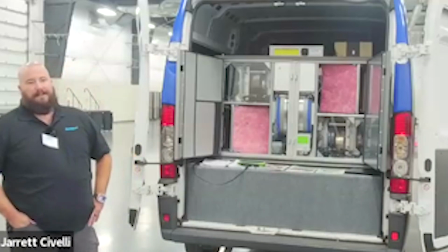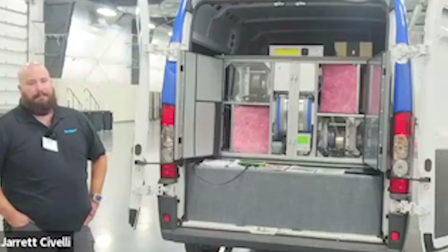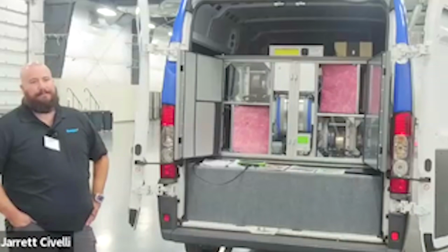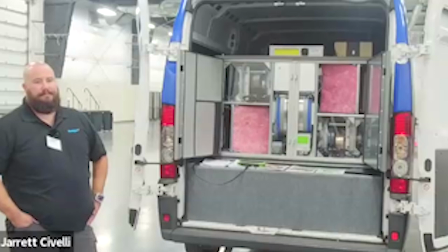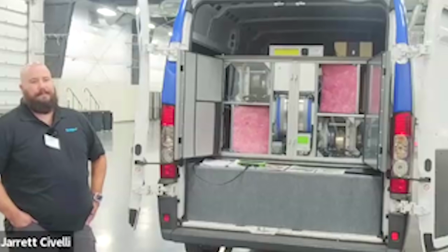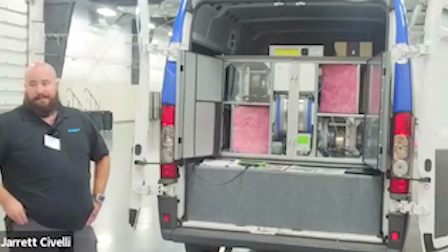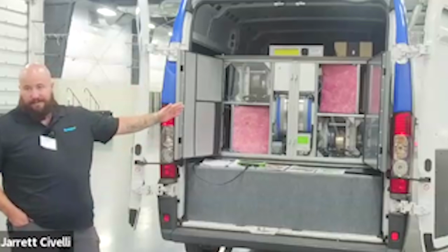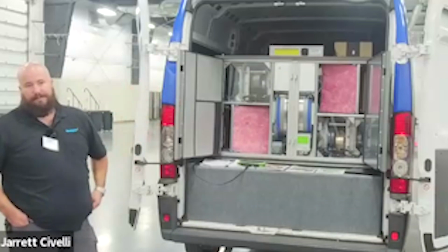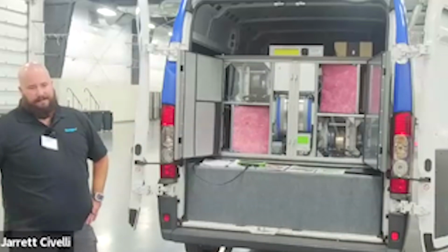Normally this technology is going to be in symphony with some other type of system for heating and cooling. And so the benefit of this is, not only are you gaining that efficient heat recovery, you could also potentially downsize existing equipment if you don't need as much capacity because you have so much heat recovery. Yeah, absolutely. So you can subtract whatever it is that you're recovering from your total energy needs and then downsize your heat plant or your chilled water plant.